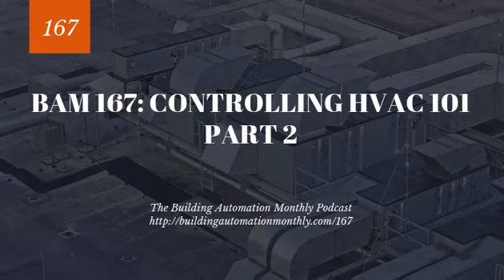It is essentially a single piece of equipment that is not really dependent on any other pieces of equipment. Now, air handlers, while this isn't always the case, air handlers tend to be systems that are utilized to serve multiple zones. Granted, rooftop units can serve multiple zones, but air handlers tend to use hydronic systems for the conditioning of their air.